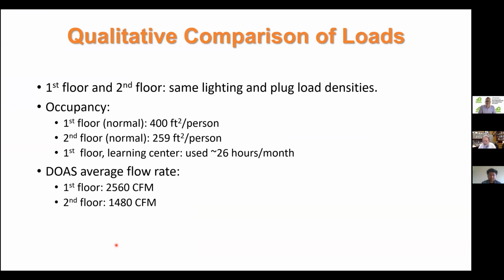So qualitatively, and this was early on when we started getting measurements, the electricity usage began to be reported. Some people from, I'll just say, the VRF industry said, oh, well, the loads are quite a bit different between the first floor and second floor. Well, we checked this, the lighting and the plug load densities are nearly identical. The occupancy, we don't have a measurement of who was there on any one day, but the first floor had about 1 person per 400 square feet, and the second floor had 1 person per 259 square feet. And the learning center was used about 26 hours per month on average.